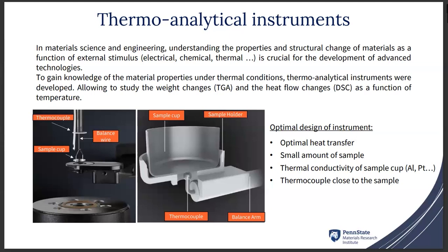This is important because those thermoanalytical instruments have been optimized to do thermal analysis. So they have been designed with an optimal heat transfer. They are using small amounts of sample in the few milligram range. The thermal conductivity of the sample cup is great, so usually we use aluminum or platinum pans. And the thermocouple is close to the sample. Despite those optimal designs, the instruments still need to be calibrated.